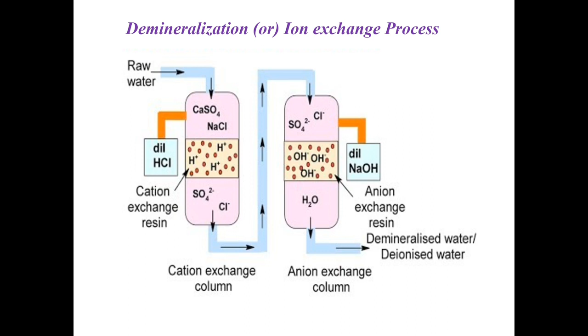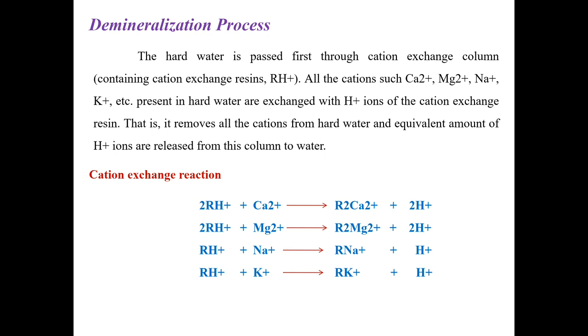In the demineralization process, the hard water is passed, as already told, first through the cation exchange column, RH plus. All the cations such as calcium 2 plus, magnesium, are bound in the cation exchange resin. That is, it removes all the cations from hard water, and an equivalent amount of H plus ions are released from this column to the water. The simple reaction is shown here.